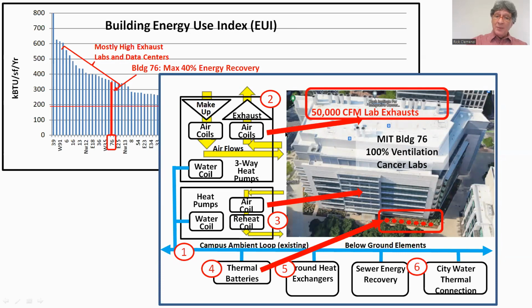Then we complement that with converting the central chilled water loop pipe to an ambient loop. All that means is you remove the thermal constraint. You go from a 42 to 45 degree outgoing temperature, and you say, we don't care what it is—anything between 40 and 90 degrees is fine. These heat pumps will all run on those temperatures. That's all fine, maybe 42. Just got to make sure you don't freeze things.